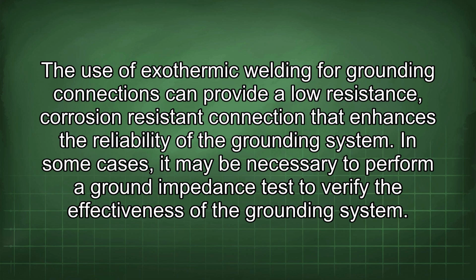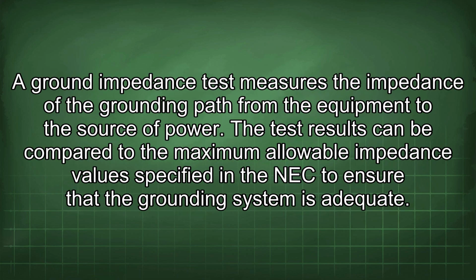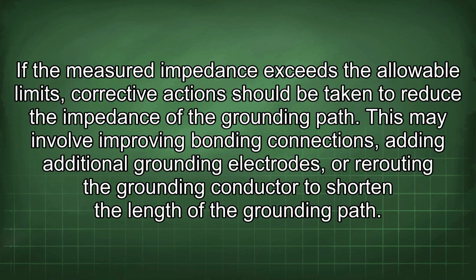In some cases, it may be necessary to perform a ground impedance test to verify the effectiveness of the grounding system. A ground impedance test measures the impedance of the grounding path from the equipment to the source of power. The test results can be compared to the maximum allowable impedance values specified in the NEC to ensure that the grounding system is adequate. If the measured impedance exceeds the allowable limits, corrective action should be taken to reduce the impedance of the grounding path. This may involve improving bonding connections, adding additional grounding electrodes, or rerouting the grounding conductor to shorten the length of the grounding path.